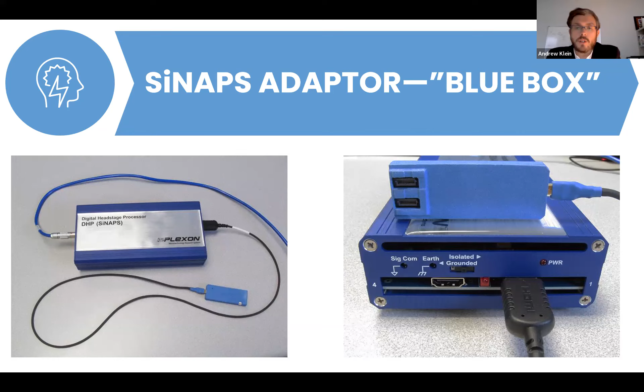Next, there are two new tester unit devices for use with OmniPlex. The first, the system tester unit, is available to the user to do just that, test the SiNAPS OmniPlex system. The system tester unit is similar to the traditional head stage tester unit offered by Plexon with traditional OmniPlex systems. This device is a new next generation head stage tester unit from Plexon and specific to the SiNAPS OmniPlex system. The system tester unit enables a user to feed up to 32 independent signals into a SiNAPS OmniPlex system via the SiNAPS adapter. The system tester unit includes its own software for creating playback files to feed into the SiNAPS OmniPlex system.